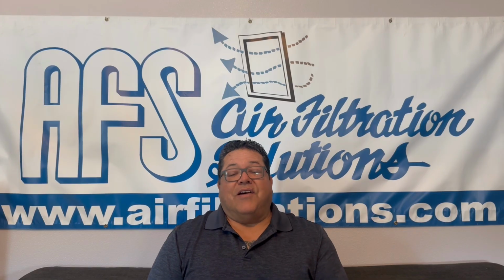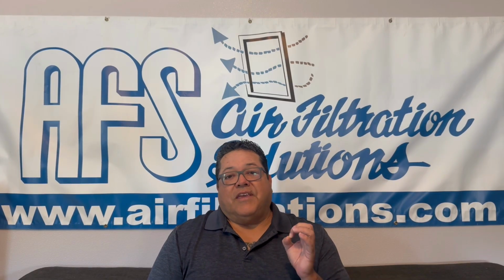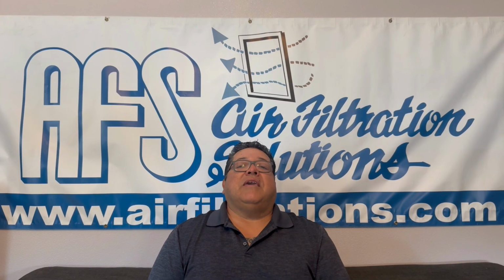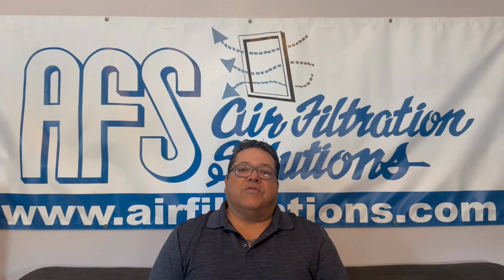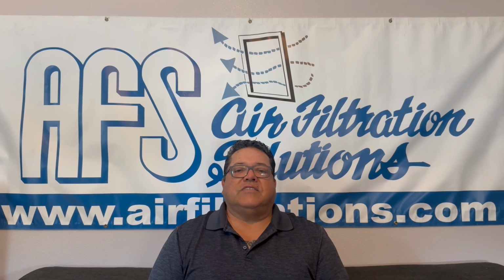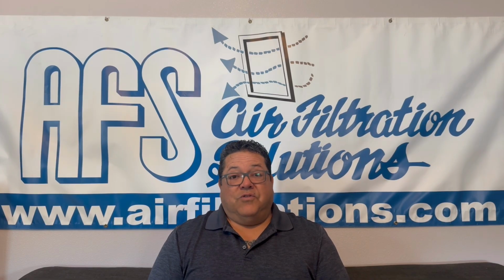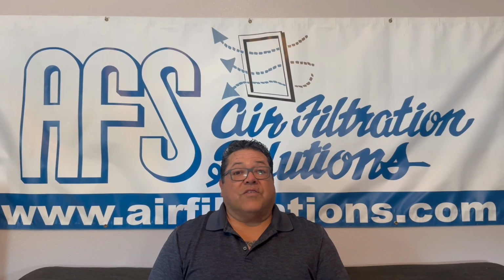And it's because your coils get dirty. An EPA released a statistic not too long ago saying that 1/8 of an inch of dirt on your coils decreases their efficiency by 21%. 21%. When you're talking about energy conservation, that 21% works against you big time.